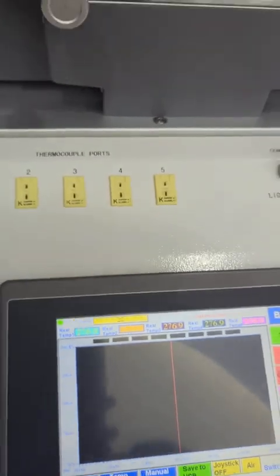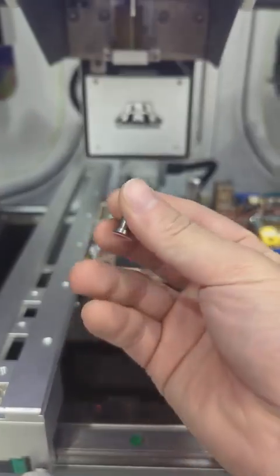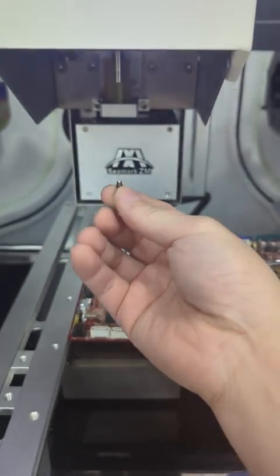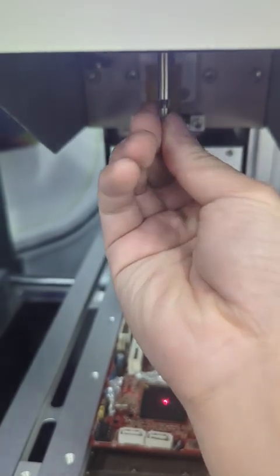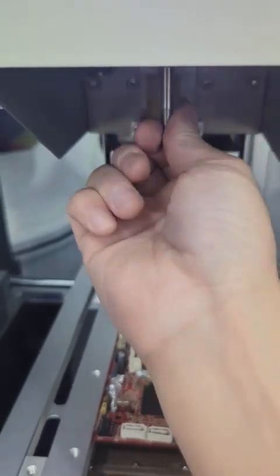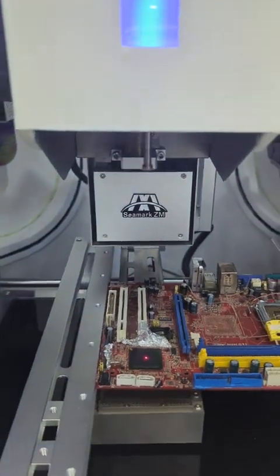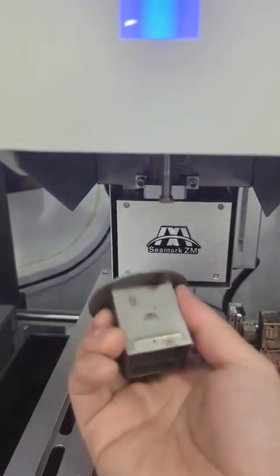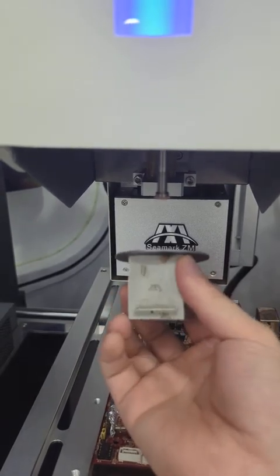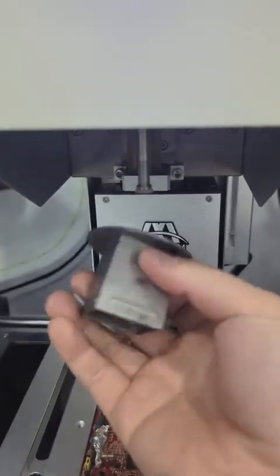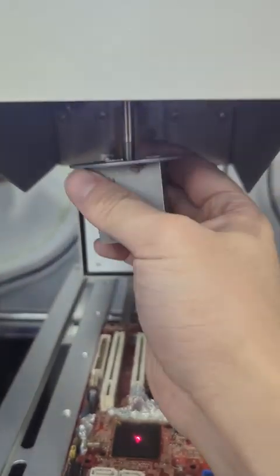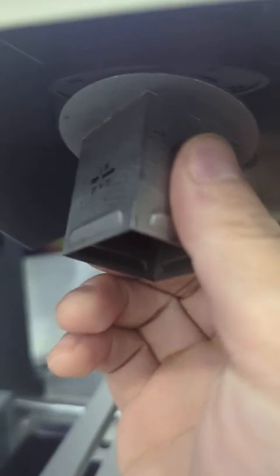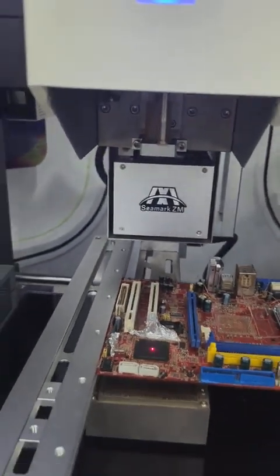And now we're going to install this vacuum nozzle and the vacuum rubber, and make sure we install it and make it tight. Okay. In calibration, we don't have to use the nozzle because we are not going to heat. If it starts to heat, we can stop it, and make sure while heating, this nozzle should be put on. If the nozzle is not on while heating, we burn out the heating element, because the sensor is there. If it's open air, the sensor might be affected by the open bed, so that's why while heating we should install the nozzle. Okay, that's just a small notice.